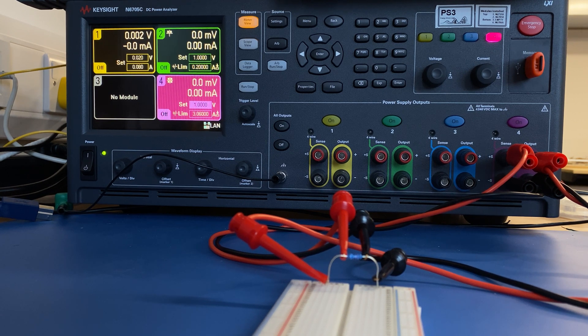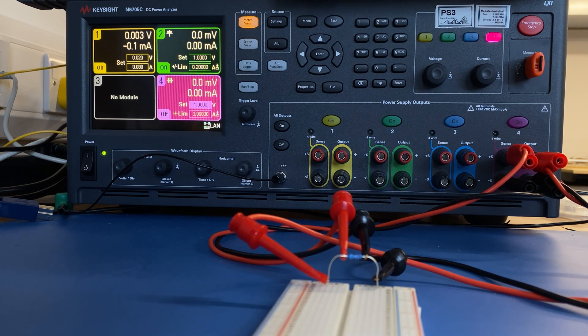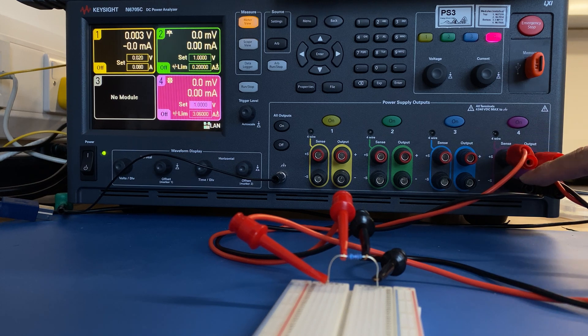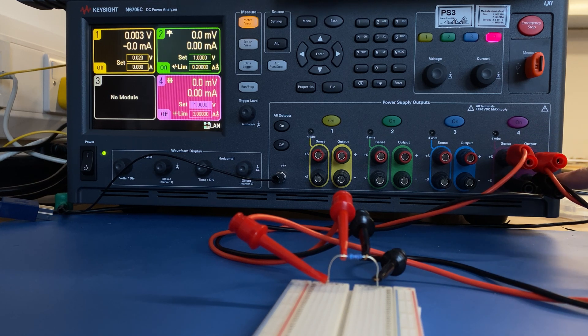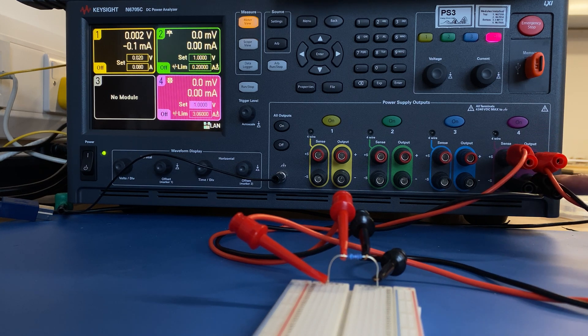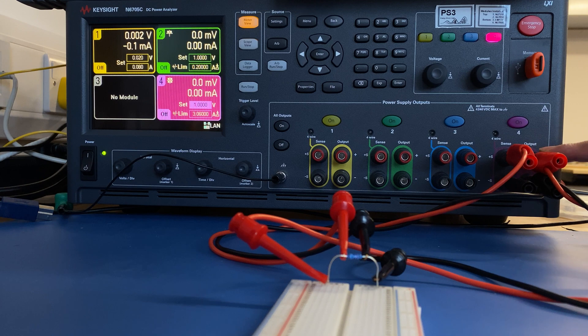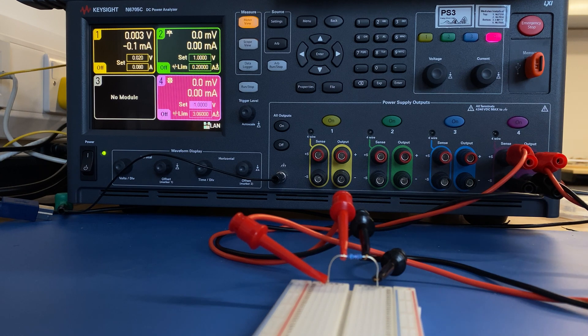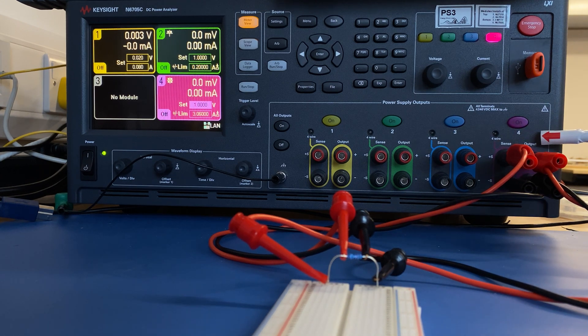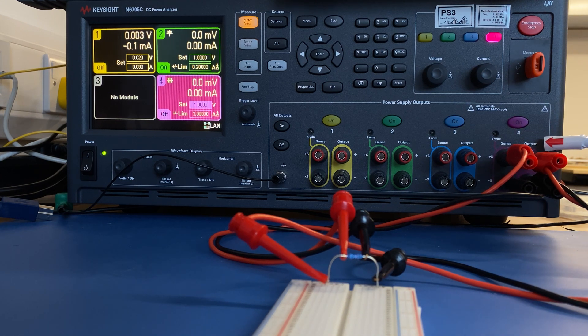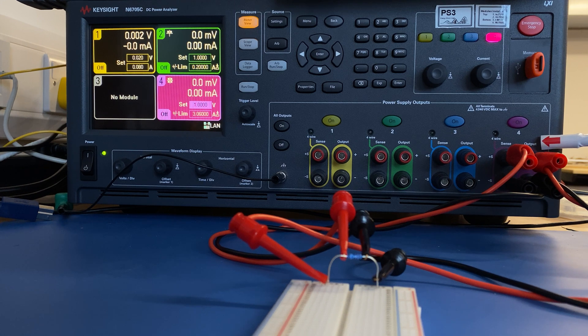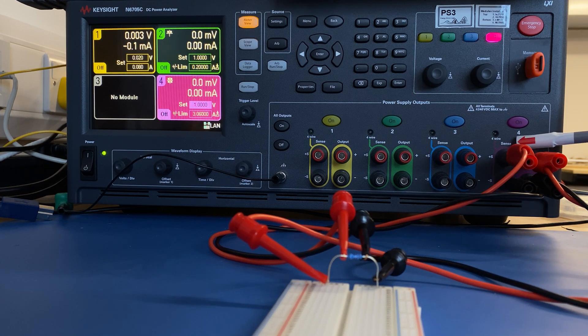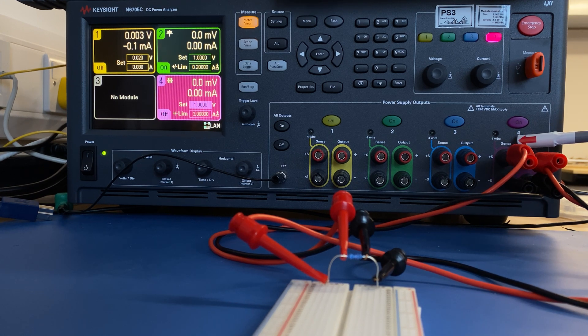To set up 4-wire, you need to have 4 separate wires. In this case, we used channel 4. We have two wires coming from output, two wires coming from sense.